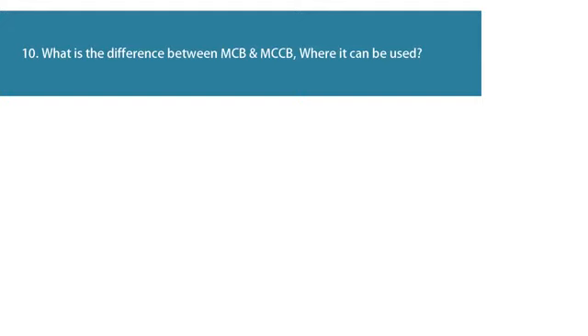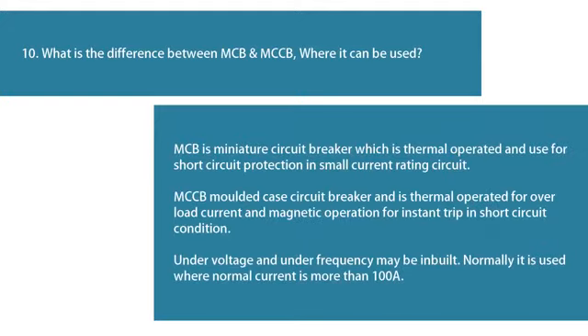Question 10: What is the difference between MCB and MCCB, and where are they used? MCB is a miniature circuit breaker which is thermally operated and used for short circuit protection in small current rating circuits. MCCB is a molded case circuit breaker — thermally operated for overload current and magnetically operated for instantaneous trip in short circuit conditions. Under-voltage and under-frequency protection may be inbuilt. Normally it is used where normal current is more than 100A.